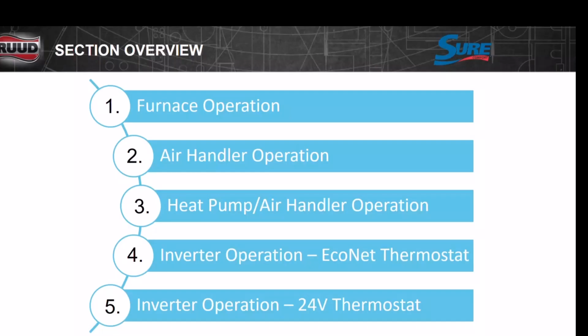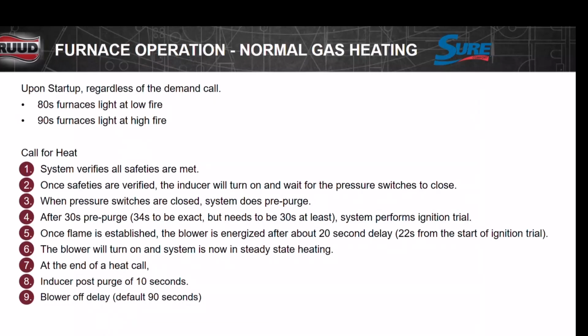Furnace operation, air handler. This is the operation sequence of the unit. Inducer: the thermostat says to start, the inducer starts. The pressure switch pulls in, the igniter starts doing its thing, then the gas valve opens up, it proves flame, and now we're heating, right? And we do the same thing again after the end of a cycle.